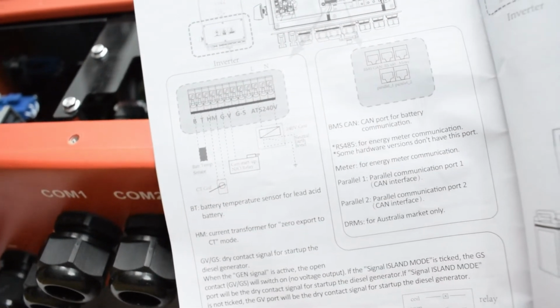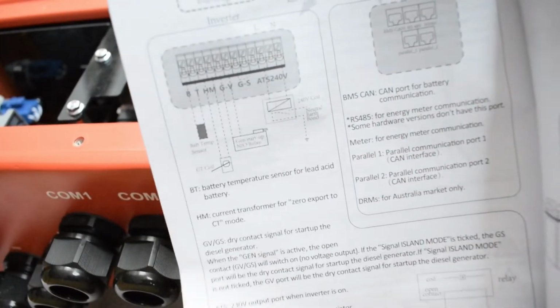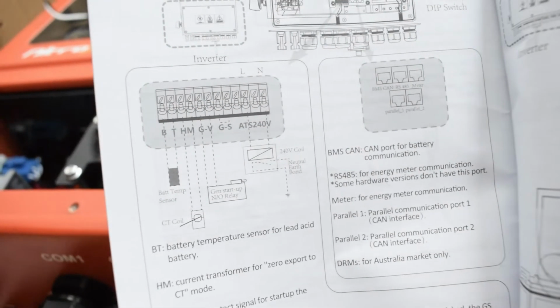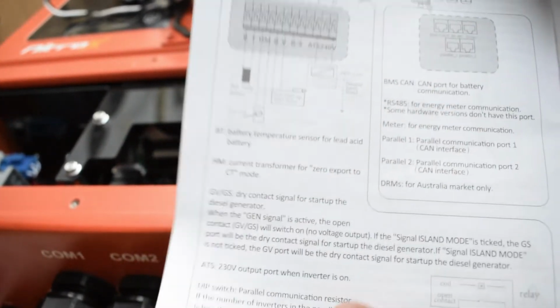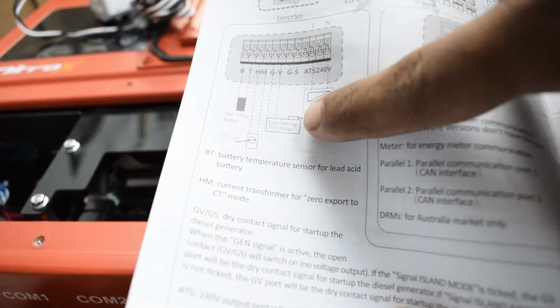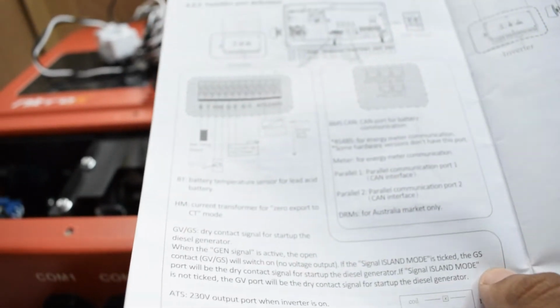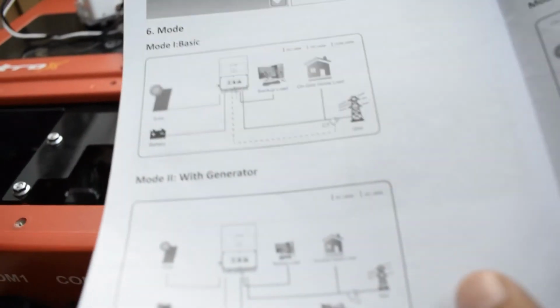Yes, this inverter can also be used as an ATS for the generator. You can convert your simple self-start generator into an automatic transfer switch generator. It can be utilized as an ATS as well. So we can connect these 2 wires with the starting coil of the generator, and when the generator starts, it sends its line and neutral and stops the starting switch. So it keeps the generator on, and when we need to turn off the generator, this ATS port will again be utilized for tripping of the generator. Okay, so now come to the ports. Yes, we explained the second mode.